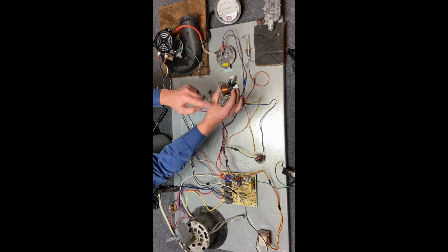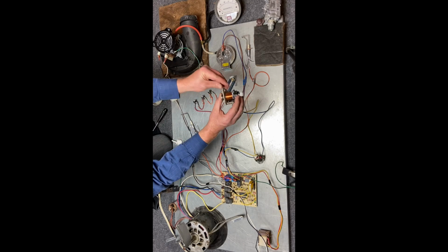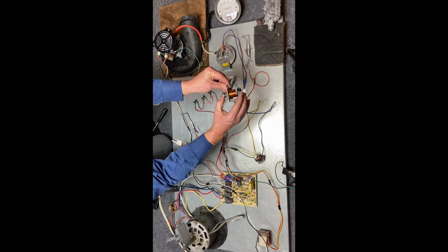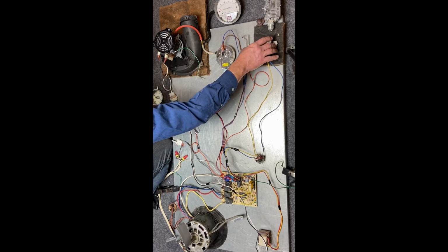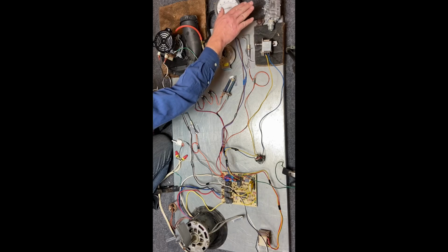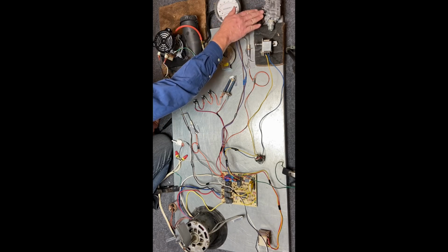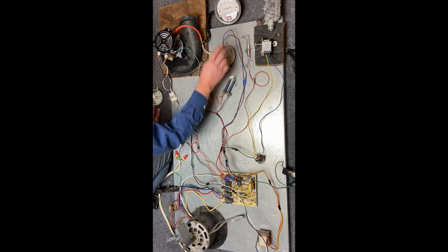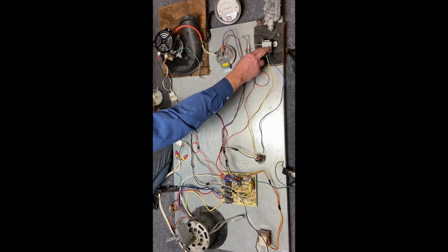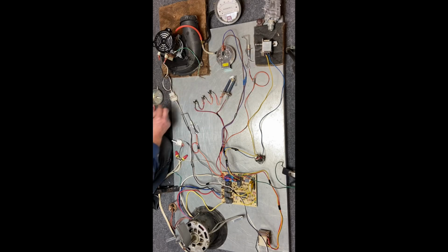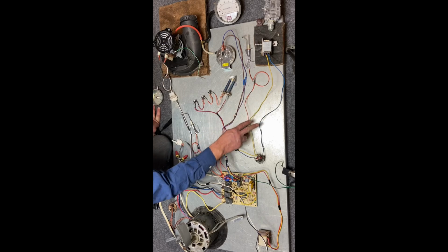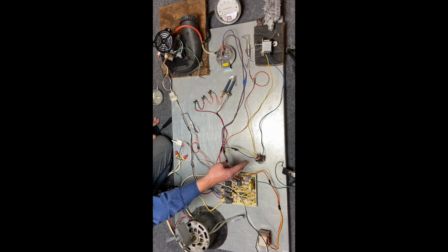So the electrons go in a circle, creating an electromagnet when it's energized. And the spring keeps it pushed down. This is the valve for a combination gas valve. Now, this is a pressure regulator, which we'll talk a little bit about later. But 2 wires energize this electromagnet. This is a 24 volt valve, and if we follow these 2 wires, it goes to a double pole switch.